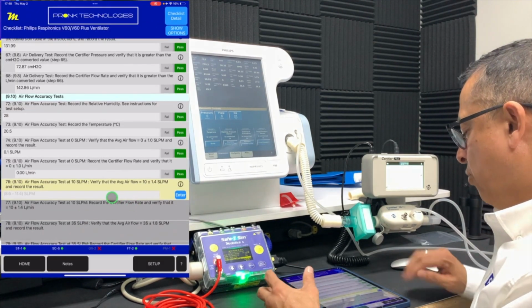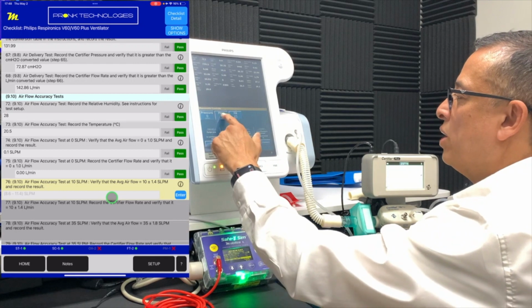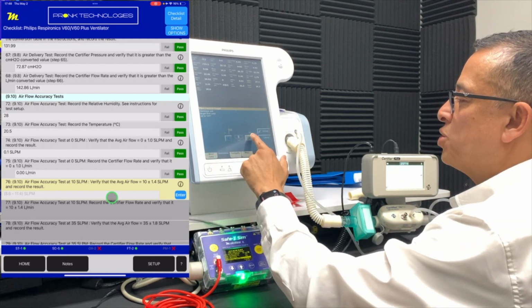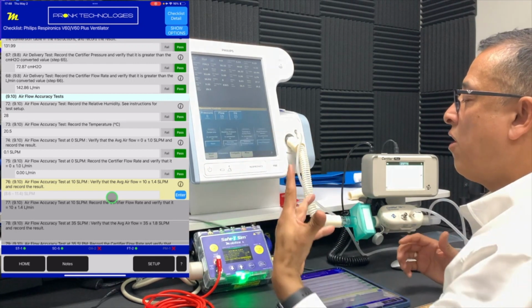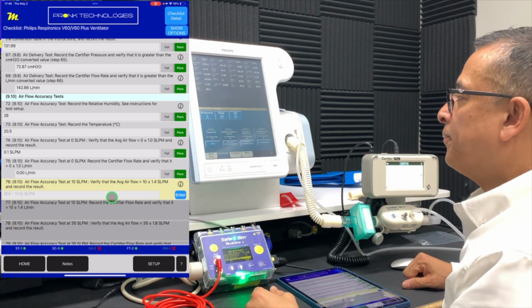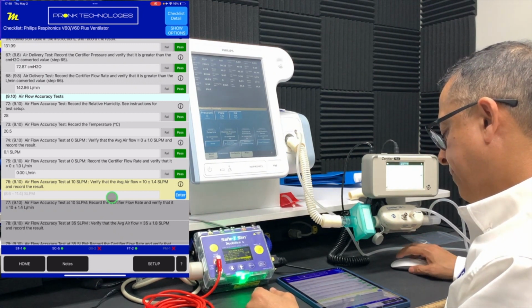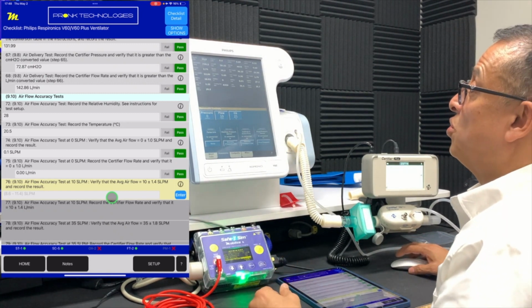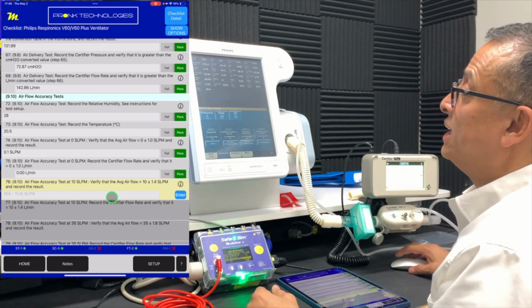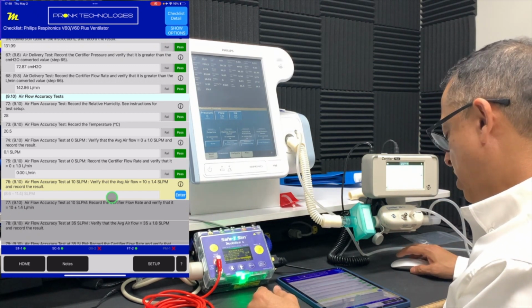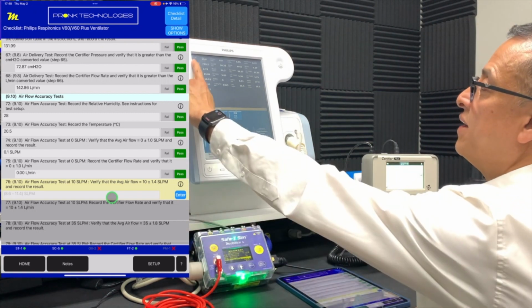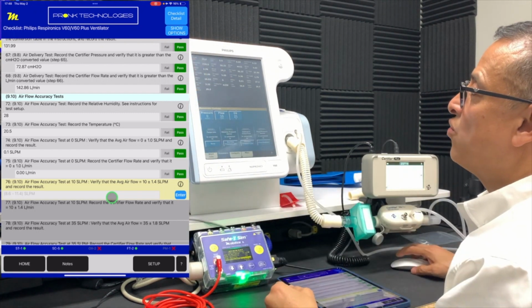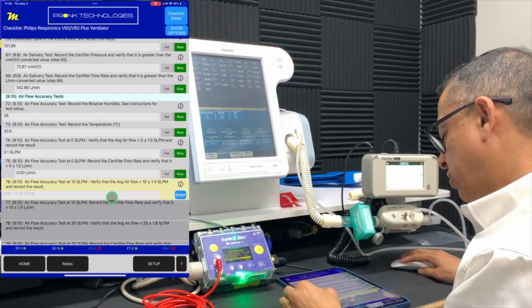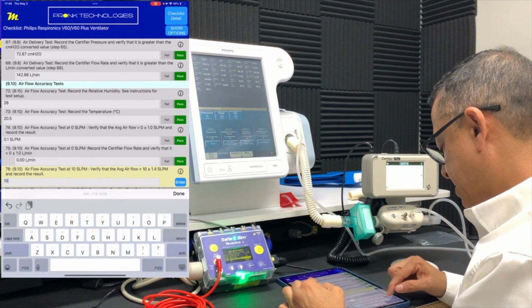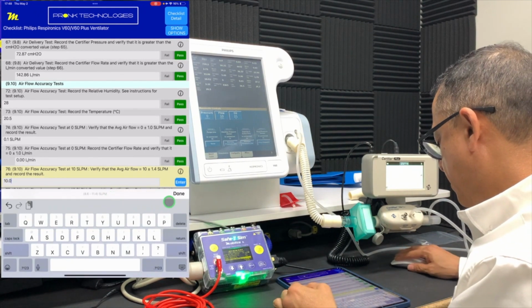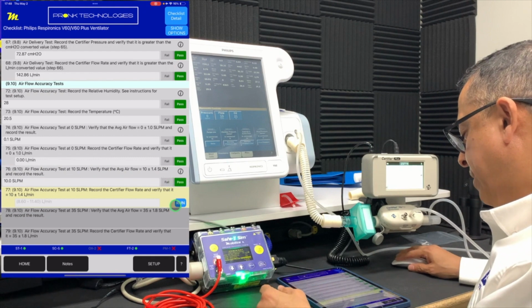And go on to now, we want to set the airflow to 10. I'm going to go ahead and do that. And we're going to make sure that these tests at various flows are indeed accurate. And now we want to make sure that our actual output is actually at 10. So we can see here, it's actually set right at 10.0. I'm going to go ahead and capture that as my reference. And then we're going to confirm that indeed the certifier measures the same value.